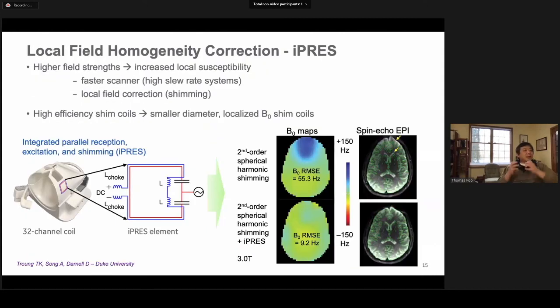In addition, at higher field strengths, you end up with higher field inhomogeneity because of higher susceptibility effects. And those can be addressed by either faster scanning with high slew rate systems or a combination of fast scanning with high slew rates and also local field correction or shimming. So these are some slides from Alan Song and Tom Trong from Duke University, showing that they've integrated these local shim coils into the receiver coils, and thereby achieving better field homogeneity correction, as you can see here.